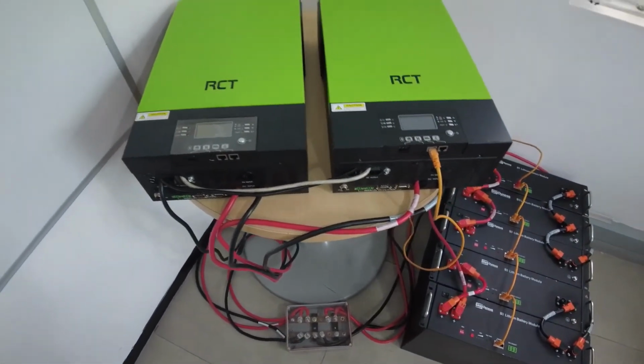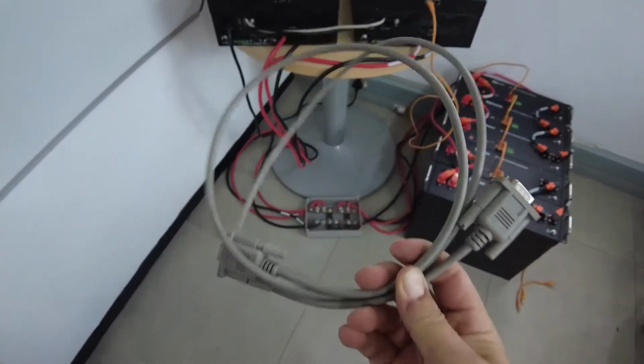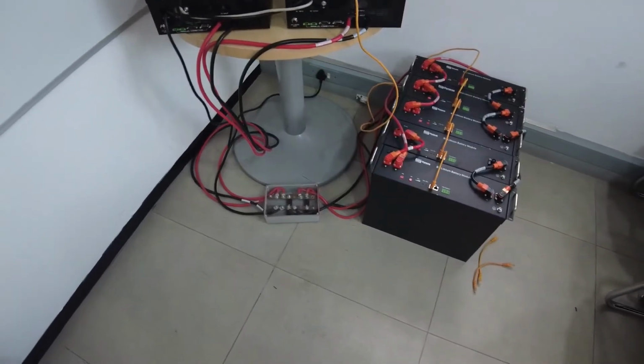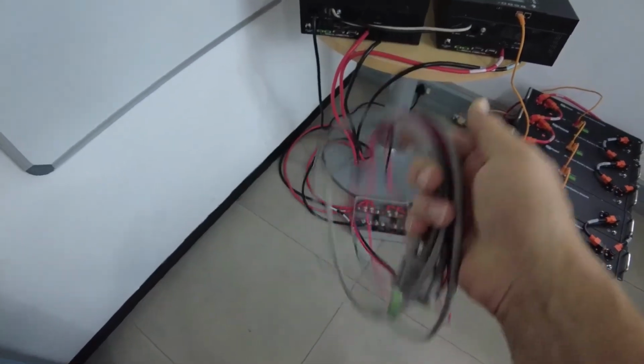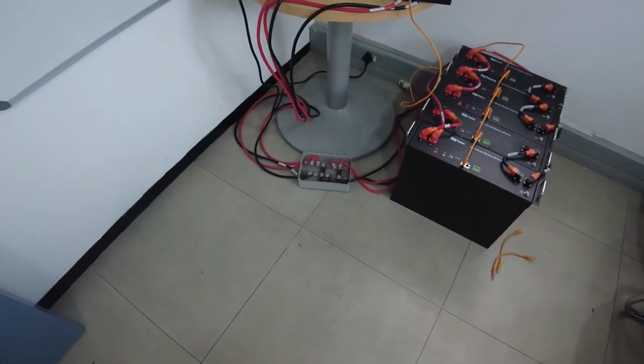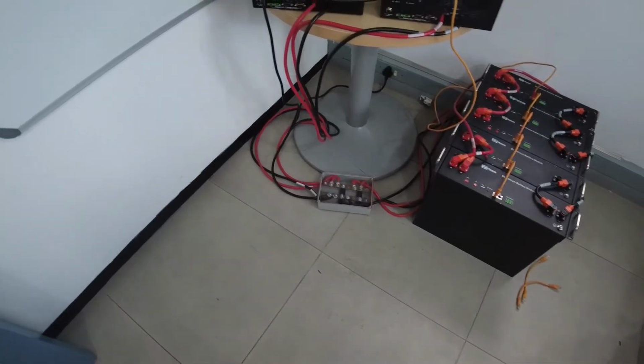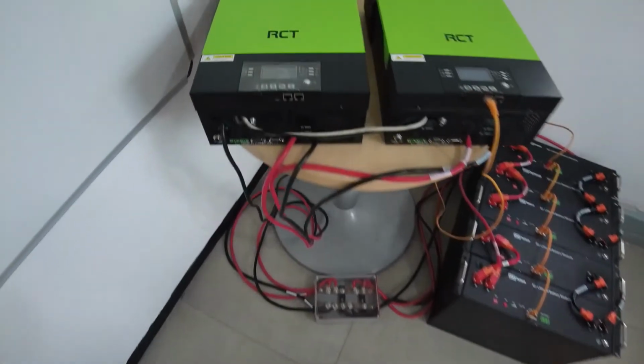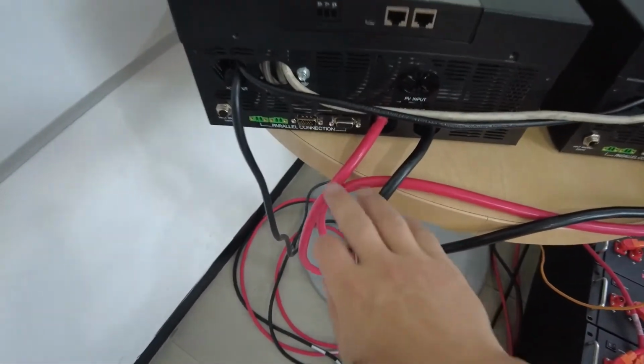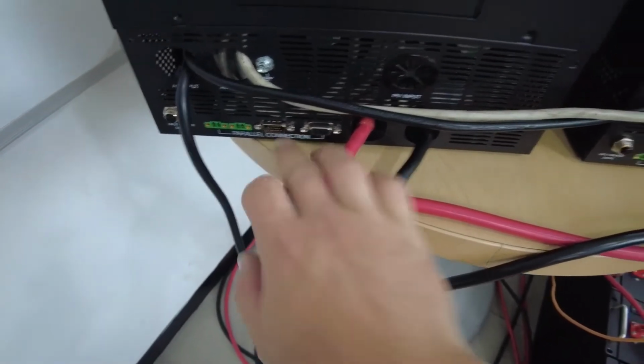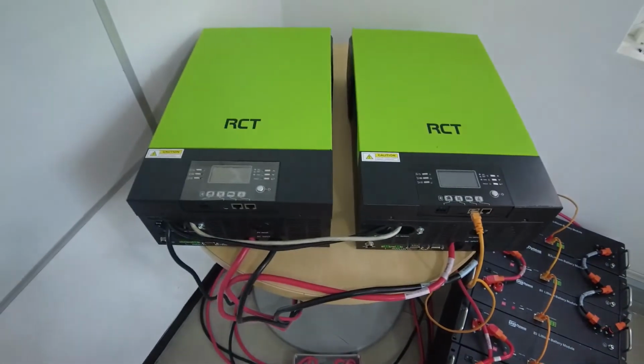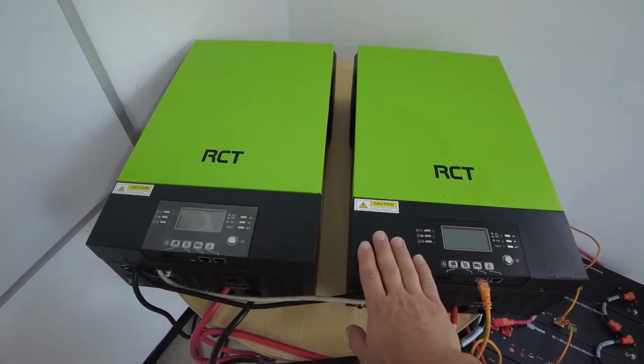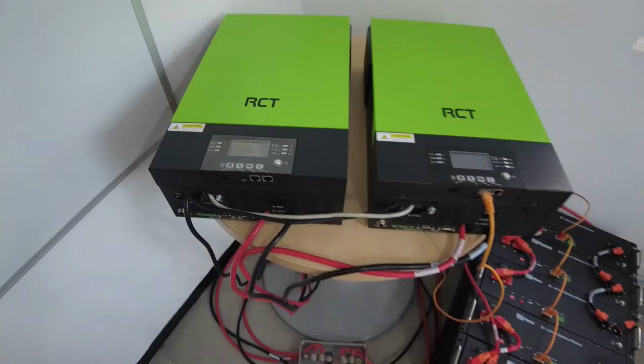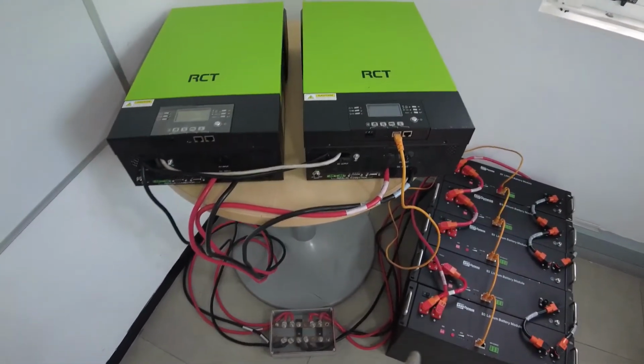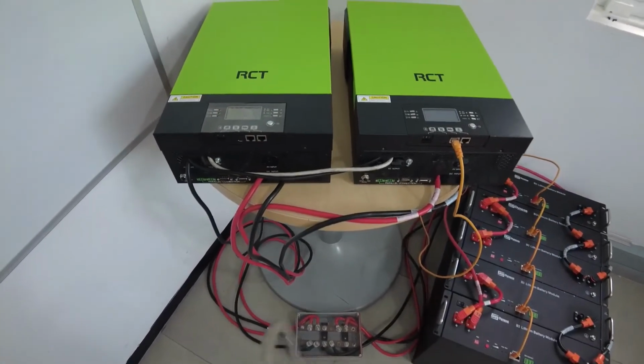Next up is to connect the parallel connection between the two inverters. With each inverter you will receive a pair of cables. One is your communications cable that we just showed, and the second is your sync cable. You will receive a pair of these cables with each inverter, so you will need two pairs of cables. Now the nice thing about these inverters is the parallel kit that's already installed in this inverter is the same. So even though this is a King inverter, it doesn't matter if you use a Max 8 kVA, Max 11 kVA, this King, or even the MKS models, even the InfiniSolar ones, they all use the same parallel cord.